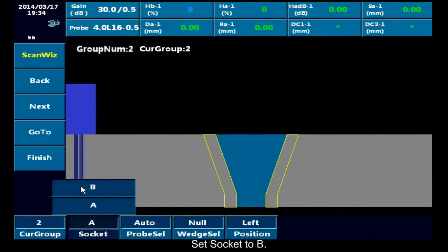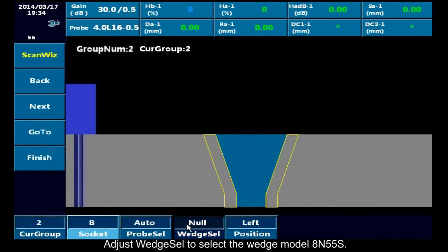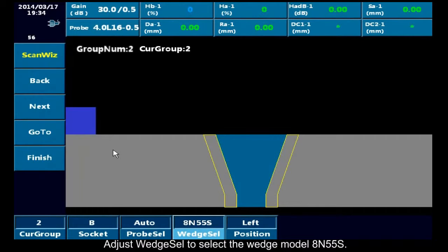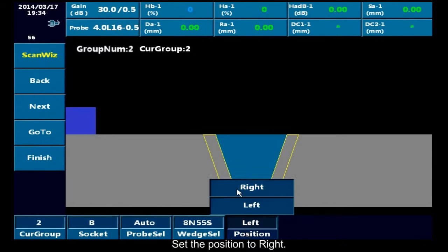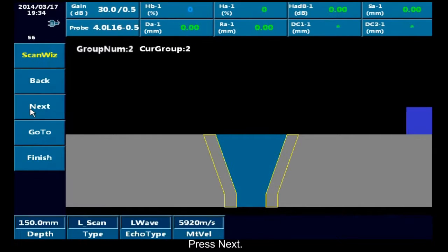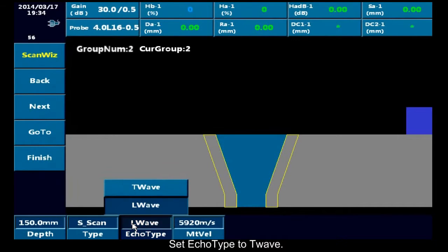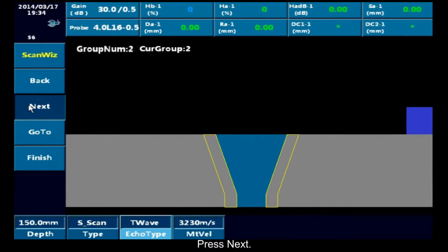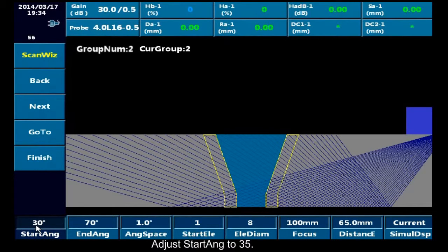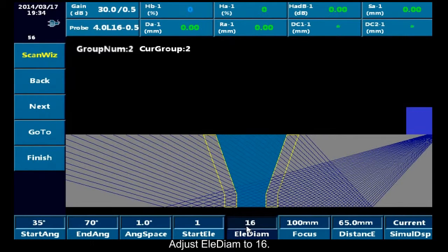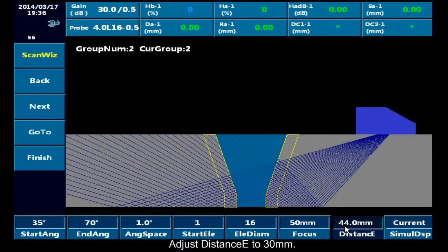Set socket to B. Adjust wedge selection to select the wedge model 8N55S. Set the position to right. Press Next. Adjust type to S-scan. Set echo type to T-wave. Press Next. Adjust start angle to 35. Adjust element diameter to 16. Adjust focus to 50. Adjust distance E to 30.